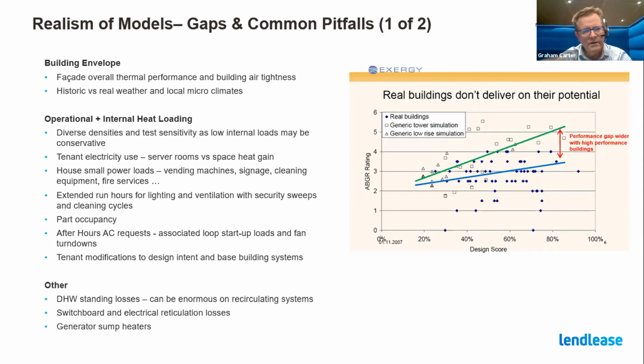With after-hours air conditioning requests, you need to be really mindful of the loop loads. You've got to warm up a heating hot water loop. You've got to cool down a chilled water loop. And the fans are operating at a really low operating point, and actually designing for that half floor occupancy, with the systems, and making sure they can turn down to that point efficiently without having to bypass air or bring on more floors is just a really important issue. In the tenant modifications to design intent and base building systems, I might touch on that when I get to tenants later on.